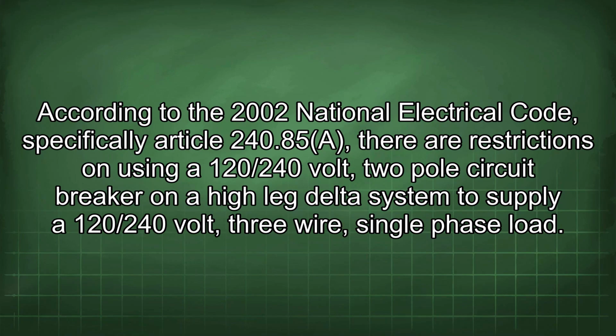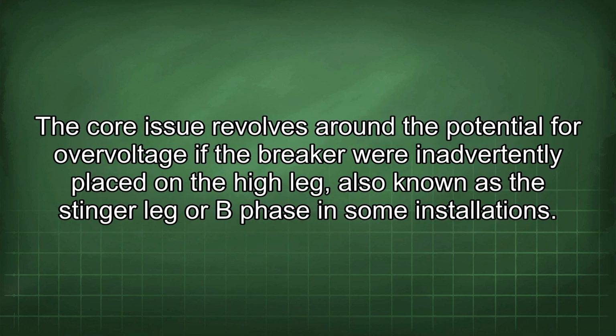According to the 2002 National Electrical Code, specifically Article 240.85(A), there are restrictions on using a 120/240 volt 2-pole circuit breaker on a high-leg delta system to supply a 120/240 volt 3-wire single-phase load. The core issue revolves around the potential for overvoltage if the breaker were inadvertently placed in the high leg, also known as the stinger leg or B phase in some installations.